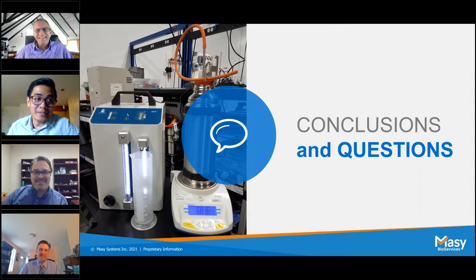Yeah, and that into, oh, sorry. No, go ahead. And to add on to Sylvan's point, again, with checking the sterilizer to make sure it's something that you want beforehand, because there's a couple times where I went in to qualify a sterilizer that was brand new and it would break down after one run. So you want to make sure that the manufacturer runs some runs on it before they release it to you, because you want to make sure that all the components and everything involved in it are working properly as well. Excellent.